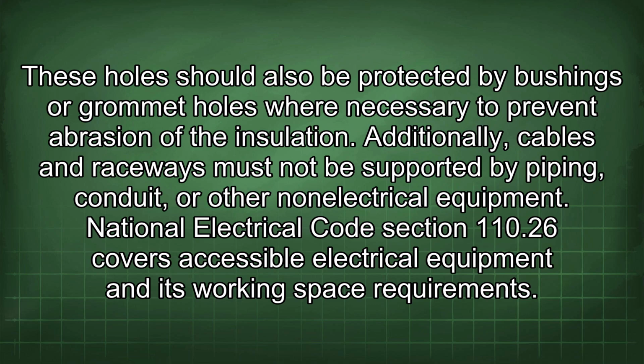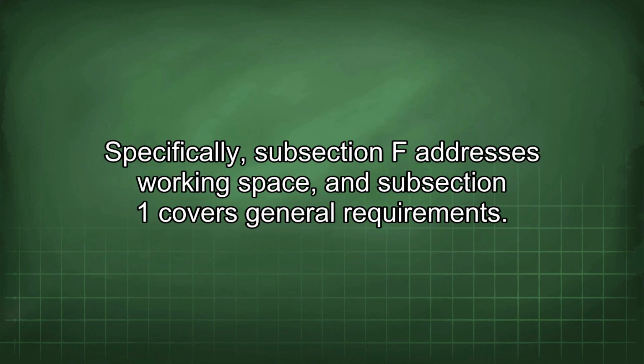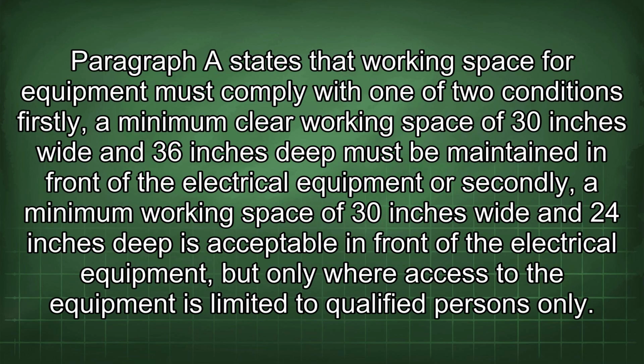National Electrical Code Section 110.26 covers accessible electrical equipment and its working space requirements. Specifically, subsection F addresses working space, and subsection 1 covers general requirements. Paragraph A states that working space for equipment must comply with one of two conditions. Firstly, a minimum clear working space of 30 inches wide and 36 inches deep must be maintained in front of the electrical equipment, or secondly, a minimum working space of 30 inches wide and 24 inches deep is acceptable in front of the electrical equipment, but only where access to the equipment is limited to qualified persons only.